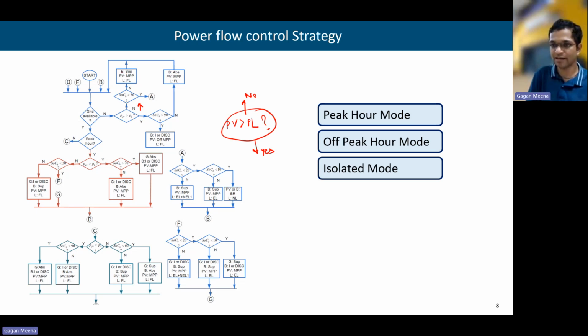The PV panel will act at its maximum power, operating in the maximum power mode, and together with the battery, it will supply the full load. But if the energy stored in the storage is less than 30%, then we need to curtail certain loads. And the logic is given here. Similar logic we have already seen in the previous week also. Now we'll check how much is the SOC of the storage. If SOC of the storage is between 20 and 30%.